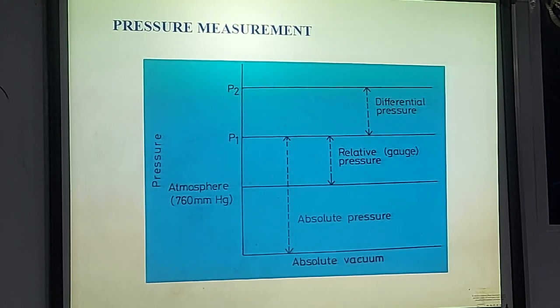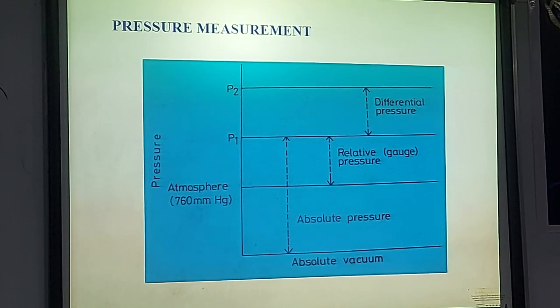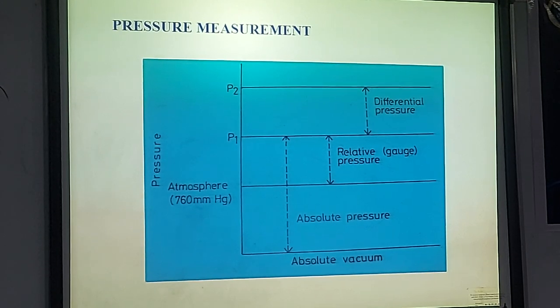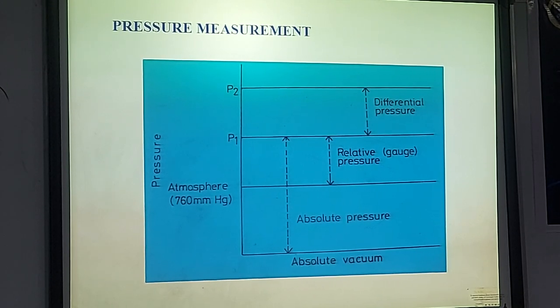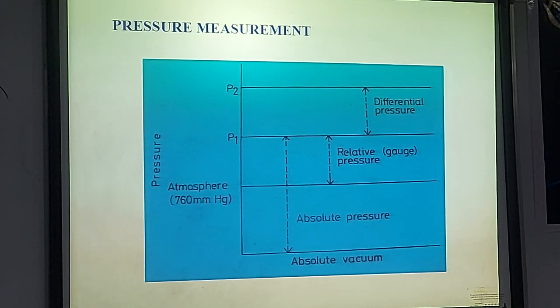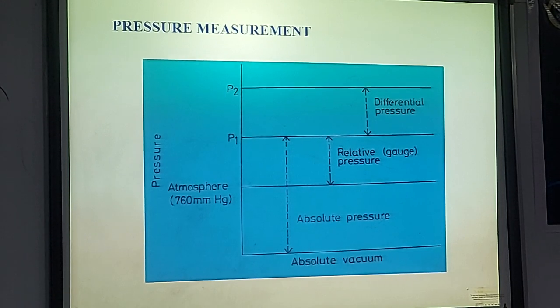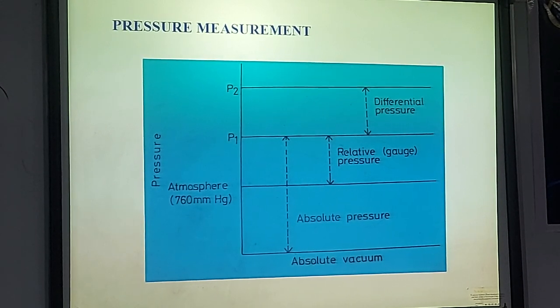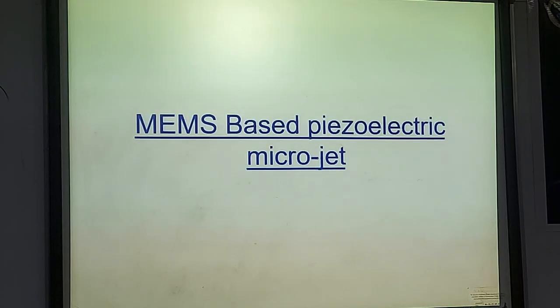Sometimes one will not be interested in measuring the absolute or relative type, but in knowing the difference between two unknown pressures, say P1 and P2. In that case, if the pressure transducer gives an indication of the difference between the two unknown pressures P1 and P2, it is called a differential type pressure transducer. Depending on how we do the packaging, we can make it either an absolute type, relative type, or differential type. So in fact, all three types we could realize.